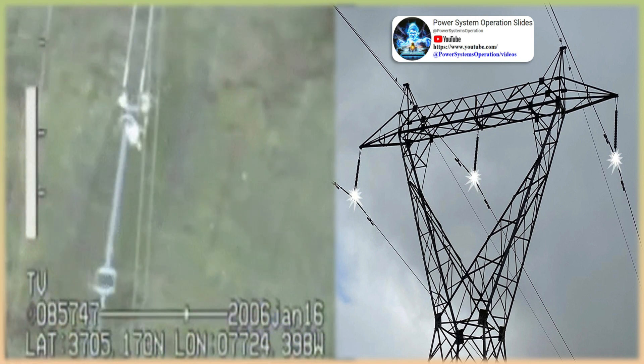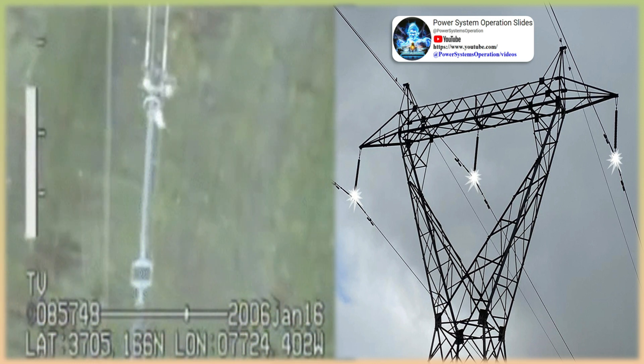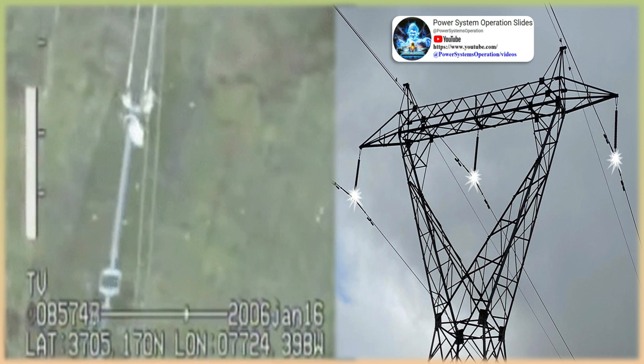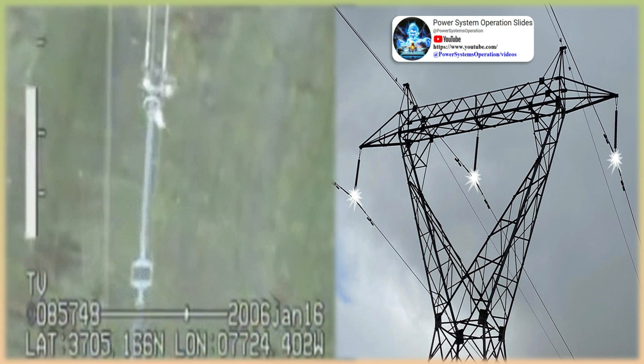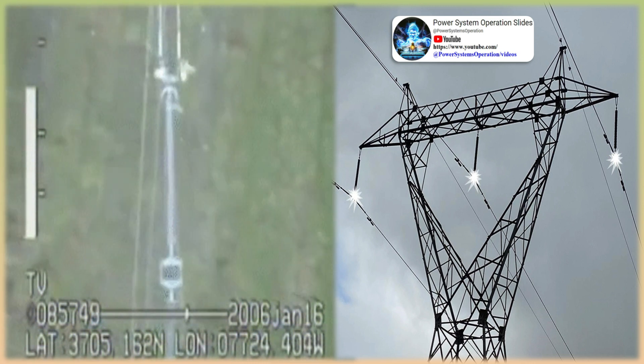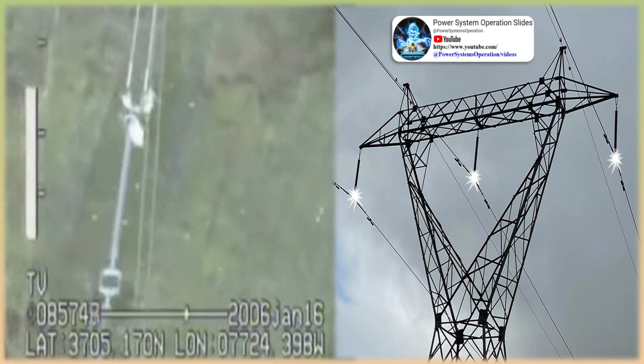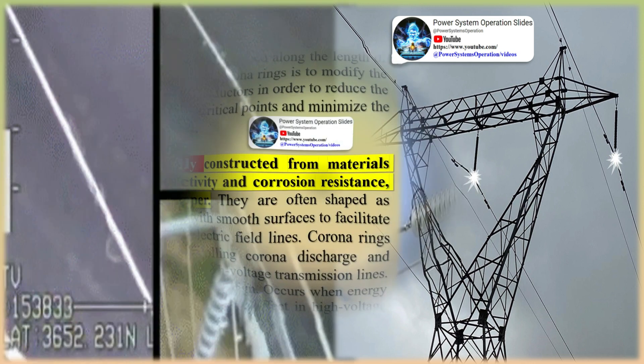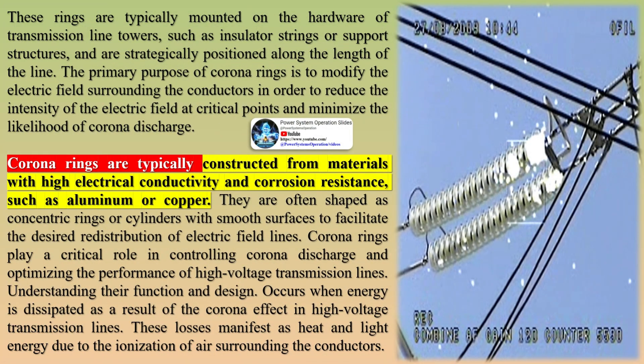A corona discharge is an electrical discharge caused by the ionization of a fluid such as air surrounding a conductor carrying a high voltage. It represents a local region where the air has undergone electrical breakdown and become conductive, allowing charge to continuously leak off the conductor into the air. Corona rings, also known as grading rings or anti-corona rings, are specialized devices installed on high-voltage transmission lines to control the electric field distribution and mitigate the corona effect.